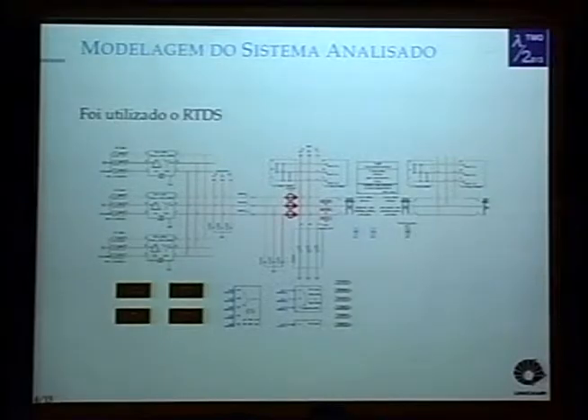The system was modeled in RTDS. This part of the work was conducted by ELSO. This is a very complex system. So here we have the current signals, current transformers here, and power transformers here. And from here is where we get the signals that are sent to the relay.